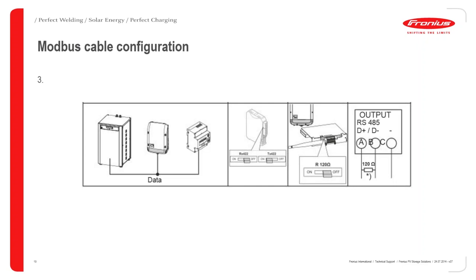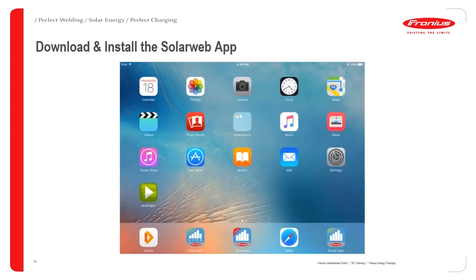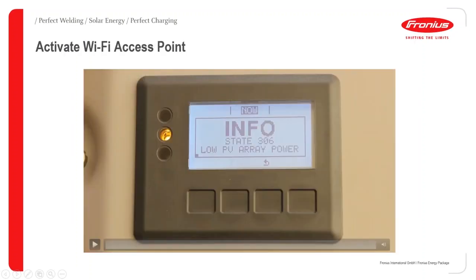So when I'm talking about that 120 ohm resistor, this is just a little bit of an excerpt out of the manual. You can see this particular configuration has the meter first, then the battery, then the inverter. So in this case, the 120 ohm resistor would be connected on the meter, which is usually stuck to the side of it, and then the inverter, so the hybrid manager, would also be set to on. The one in the middle is a battery, which is on the uni gate. That would be set to off because it's in the middle. So the other constellation as well, if the meter's in the middle, then you wouldn't have to bother putting the 120 ohm resistor in the middle. Or if you've got the inverter in the middle, then that's when you would switch off that 120 ohm resistor on the hybrid manager because it's in the middle there.